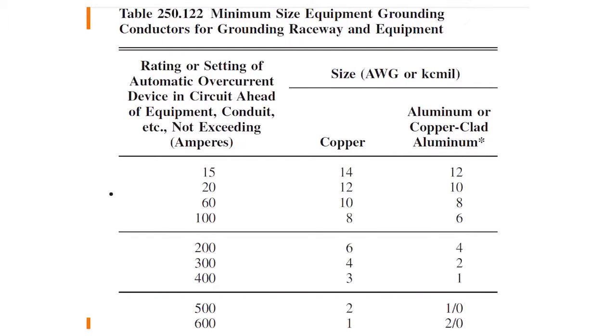So that's the easy. So you see here, we can use number 10 copper as an equipment grounding conductor up to a 60 amp overcurrent device. Okay, well at 30 amps, it is the same size. And so at 40, 50, and 60 amps, it is undersized. And so that's the break point for undersized, anything above 30 amps.